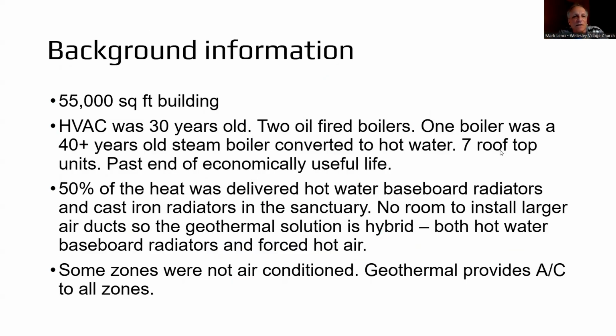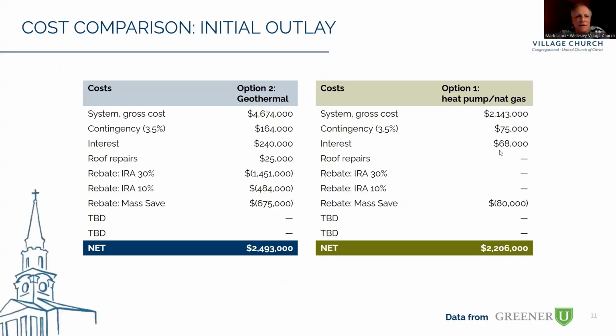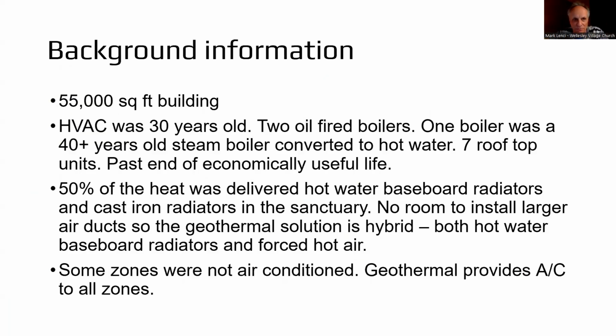This is a quick rundown of what we have: a 55,000 square foot, 100-year-old brick building heavily expanded and modified in 2000. The HVAC was about 30 years old—2 oil-fired boilers converted from who knows what, they could have powered the Titanic. Half the heat was delivered by baseboard hot water, half by air. There was no ability to modify the building for bigger air ducts to go to a simple forced hot air or cooling solution, so it had to remain this hybrid of baseboard radiators and forced hot air. It also expanded the scope of what we had to air condition in all the rooms.